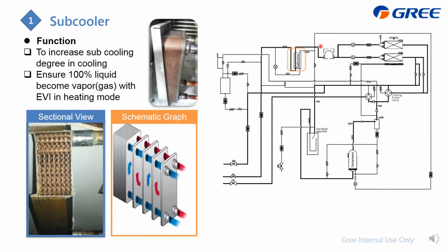Subcooler is located here just after the IPM cooler and the outdoor heat exchanger. Here is the working theory. You can find that this is the plate on the left side and the right side. There are 2 different flows. We make them exchange heat inside. And this is the sectional view. You can find that this one is actually the plate. It is not flat. We make it uneven just to raise the heat transfer efficiency.